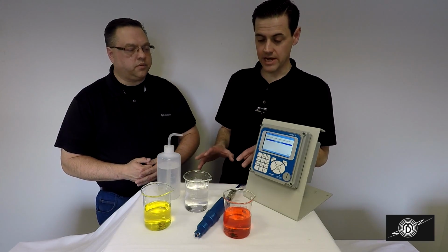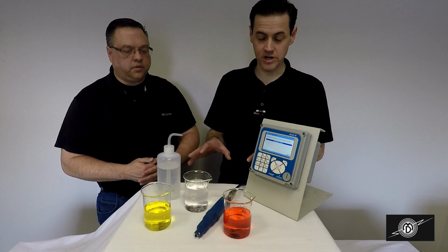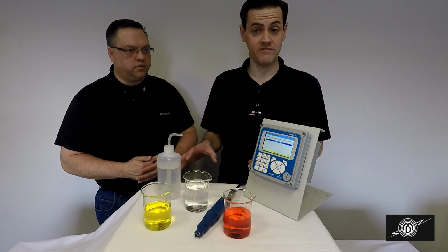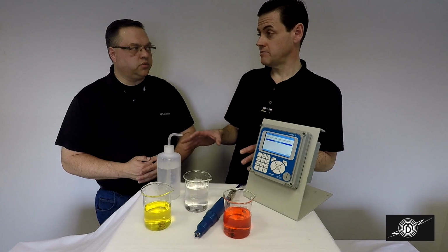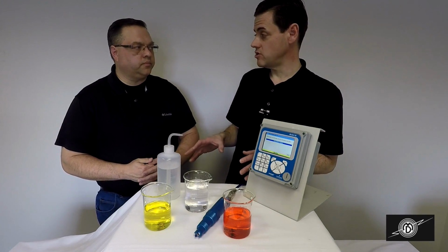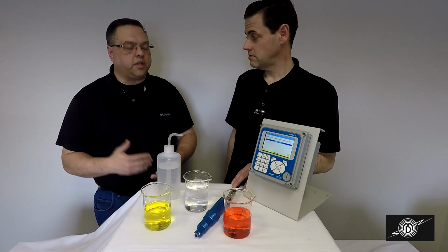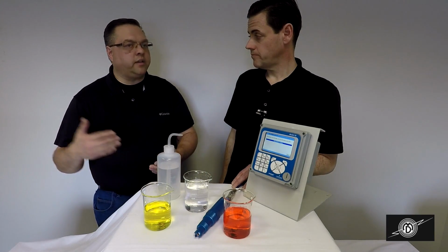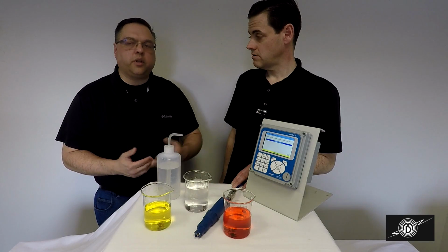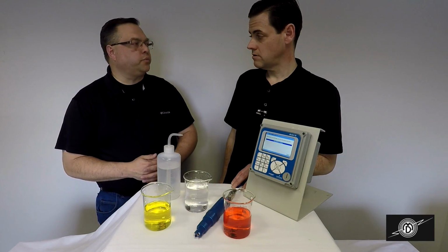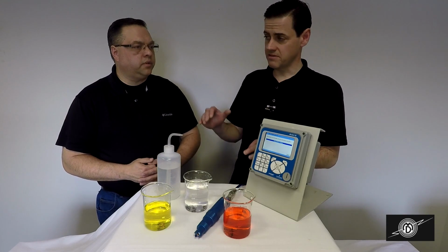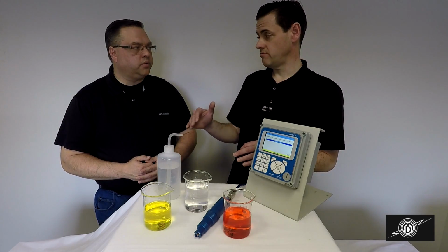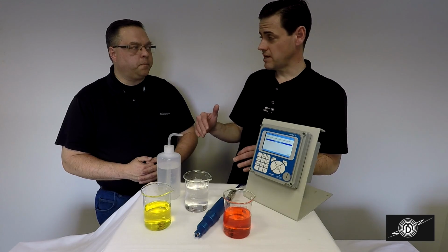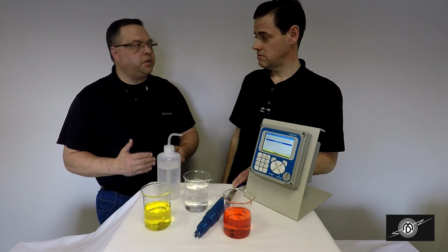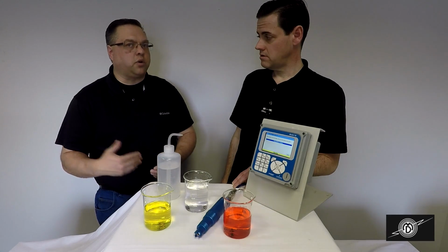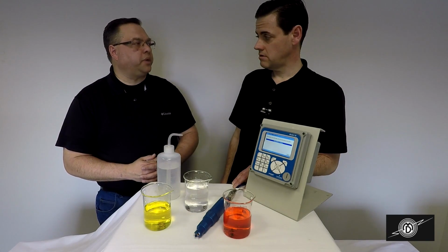Okay, now in this particular case, we have all our buffers and wash solutions at room temperature in preparation to make a quick video, but sometimes when it comes out of, say, a hot process or something like that, we're going to need to cool the sensor, correct? The best thing to do, if the temperature of your probe has been elevated above ambient, is just pull it out, put it in a container of water, and let it cool down to room temperature. Now, how stable does the temperature have to be? I mean, if it fluctuates at 0.1, 0.2, 0.3 degrees Fahrenheit or Celsius, should I be concerned? No, not too bad. But if it starts getting to be 2 to 3 degrees fluctuation or above ambient, wait a few extra minutes for it to come down.